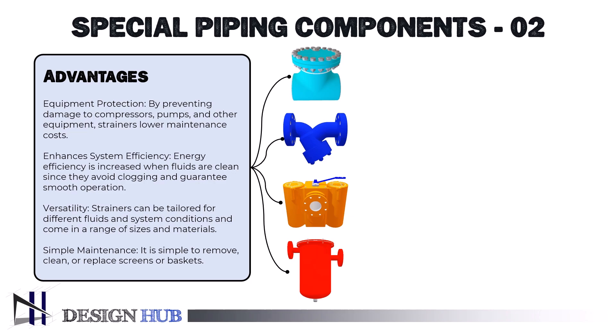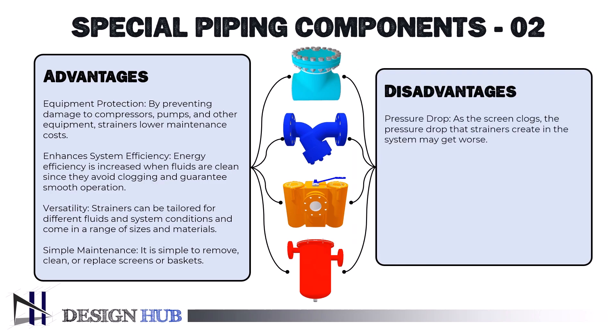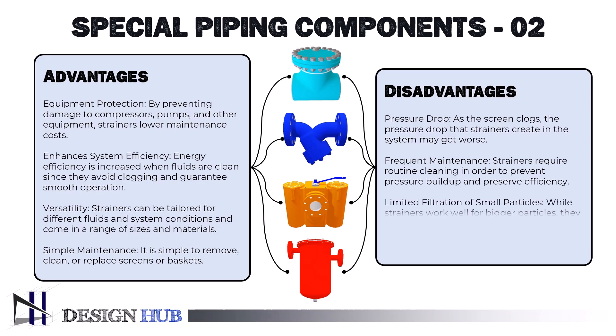Now let's see some disadvantages. Pressure drop: as the screen clogs, the pressure drop that strainers create in the system may get worse. Frequent maintenance: strainers require routine cleaning to prevent pressure buildup and preserve efficiency. Limited filtration of small particles: while strainers work well for bigger particles, they could miss finer ones, necessitating further filtration for extremely pure systems.